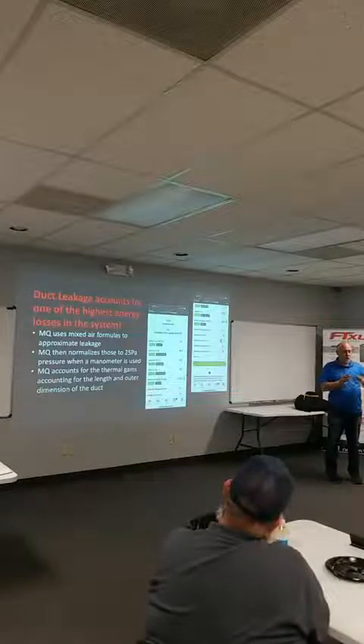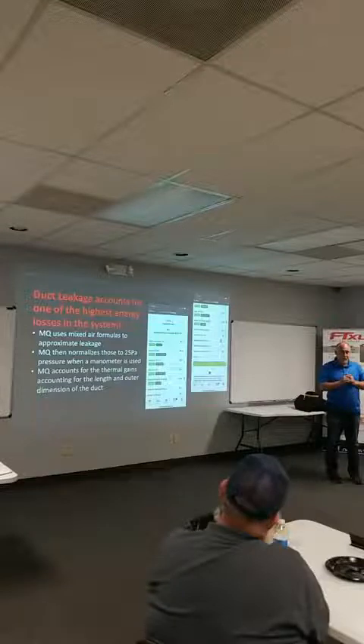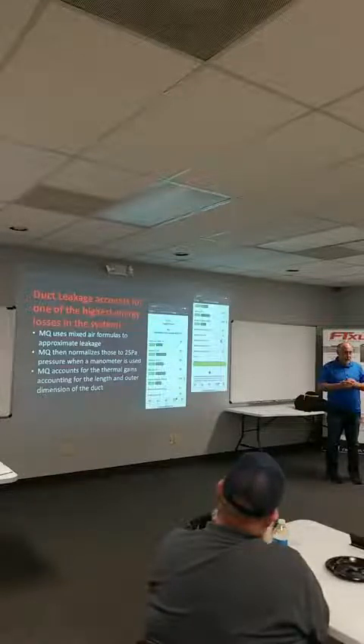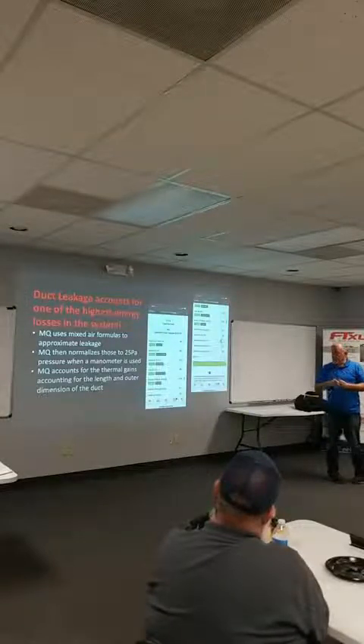Have you ever seen a coil load up funny where half of it's covered with dirt and half of it's spotless? That's because the coil's not getting to an even temperature. Half of it's dry, so it's not rinsing the dirt off. It should never have gotten there because the filter was blocked, right?